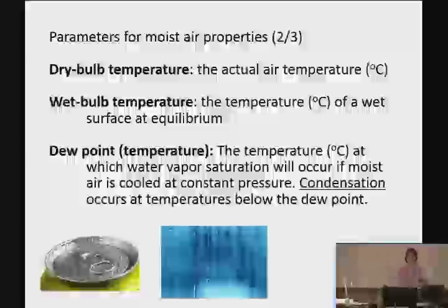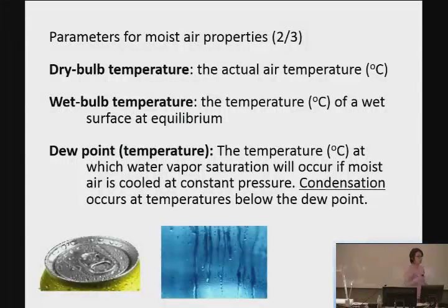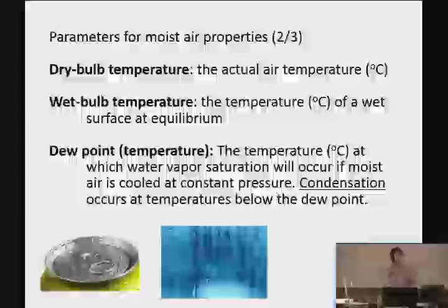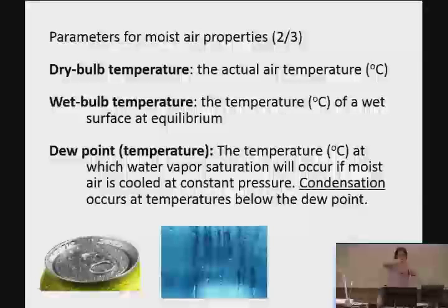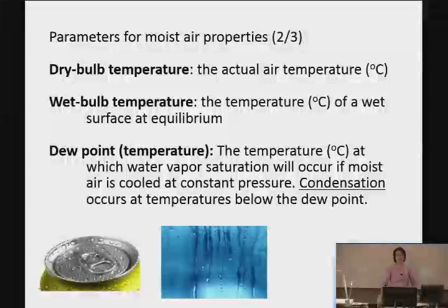Okay? All right. You did a lot already. Good. So you understand dry bulb, wet bulb. So then I have sensors if you want to see a wet bulb temperature sensor. It's very primitive, just a sensor wrapped with cloth, and then we have to soak it with DI water, because the salts affect it, so we have to use DI water. But anyway, if you are interested to see that, I can show you. We use that for calibrating the humidity sensor. Because knowing wet bulb and dry bulb, you can find humidity, relative humidity, absolute humidity.